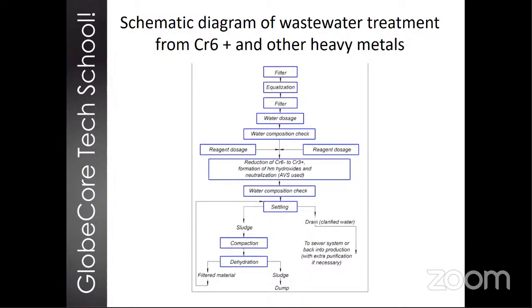First, we reduce the chromium in an acidic medium at pH 2 or 3 with sodium bisulfite, and subsequent neutralization with alkali. In the cases listed above, reagents should be fed directly into the device, or maybe directly upstream from the Vortex Layer device, not in front of the pump. We do this to avoid overgrinding of the resulting solid hydroxides that we receive in the process.